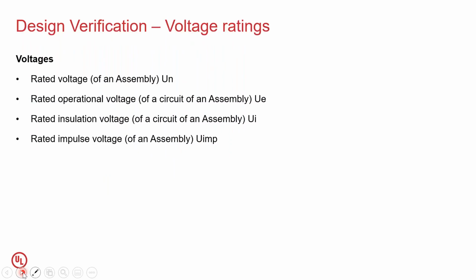Let's spend some time on the different voltages that are applicable for any busway system. You have the rated voltage of the assembly. Whenever you have a plug-in unit, it is possible that the overall rating of the busway could be 1000 volts, and your plug-in circuit can be rated at 600 volts. This is what we mean by different circuits having different operational voltages. The overall busway can be rated for a higher value if you so require, or alternatively the overall rating can still be 690 volts and your circuit operational voltage can also be 690 volts, depending on your situation.